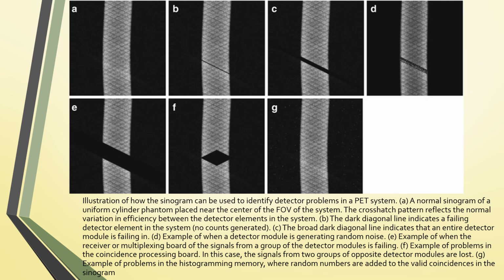With C, you have a broader, dark diagonal line that indicates an entire detector module is failing. And D is an example of when a detector module is generating random noise. E is an example of when the receiver or multiplexing board of the signals in a group of the detector modules is failing. Keep in mind you have several PM tubes in one detector block, but then you may have a group of detector blocks that all have the same power supply and circuitry coming from them. So that will cause a much larger black space, just what you see in E.